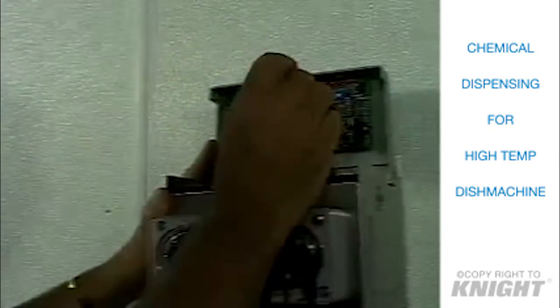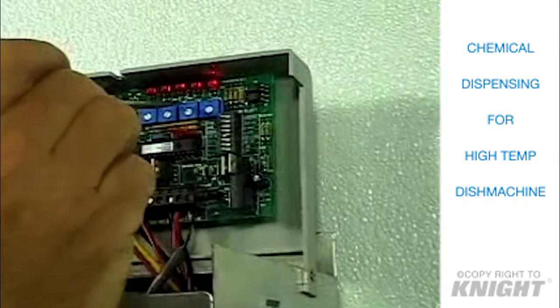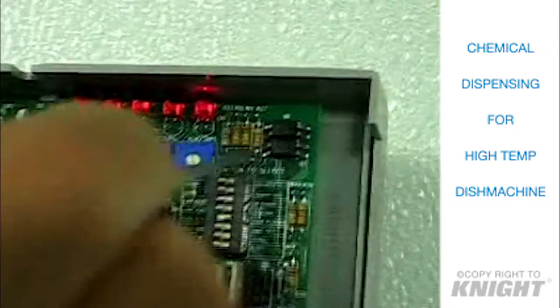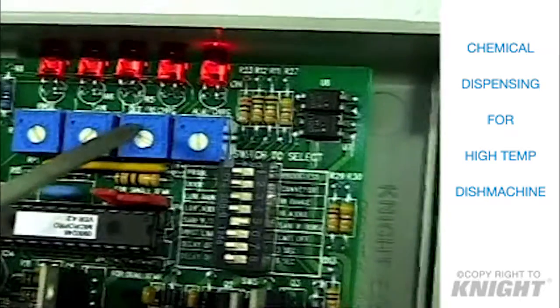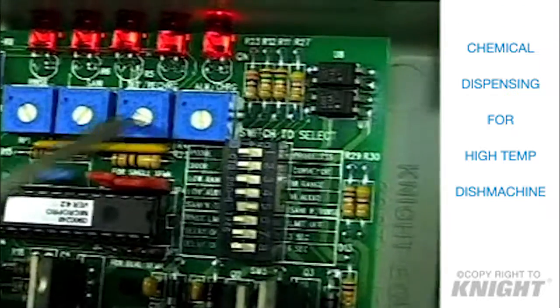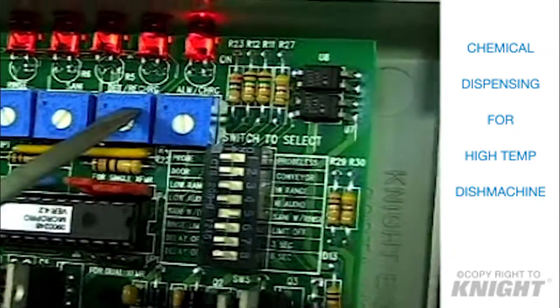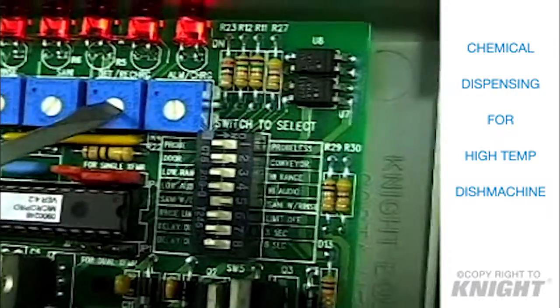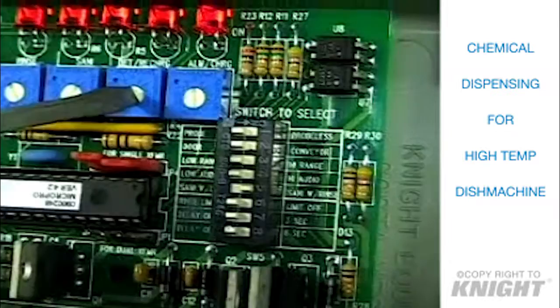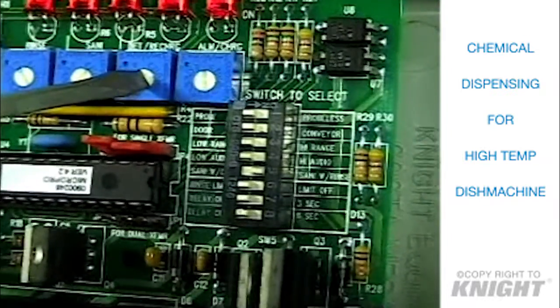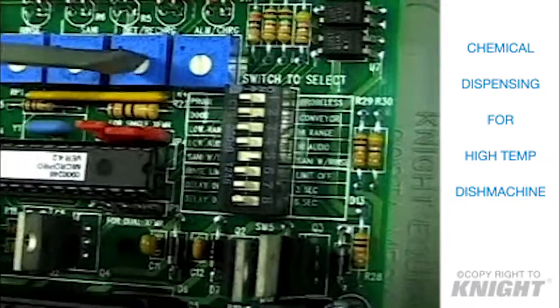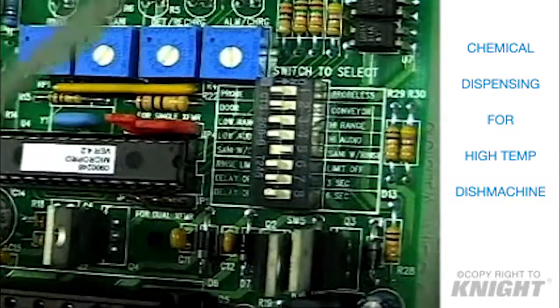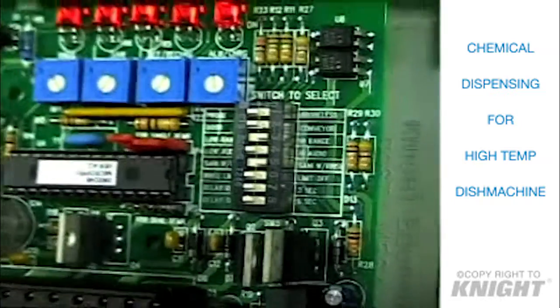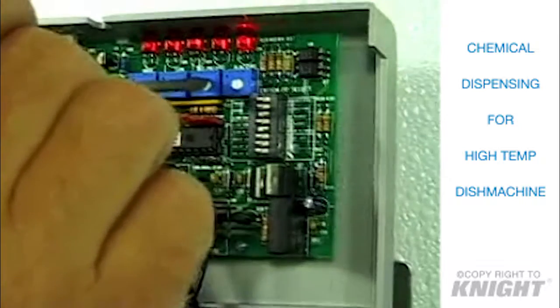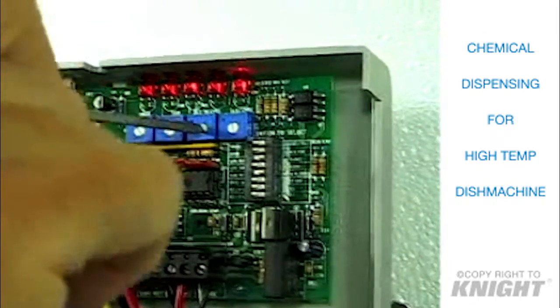The detergent, and if you look at this closely, it says detergent and recharge. That means that if it's in probe mode, this is the detergent concentration potentiometer, and if it's in probeless mode, it's the recharge potentiometer. So in detergent mode, the farther I turn this potentiometer to the right, the more detergent I'm going to get. If that's still not enough detergent, I'm going to turn it all the way back to the left, and I'm going to flip this from low range to high range, which is like simulating being able to turn this potentiometer twice. And then in high range, I can turn it all the way to the end again.